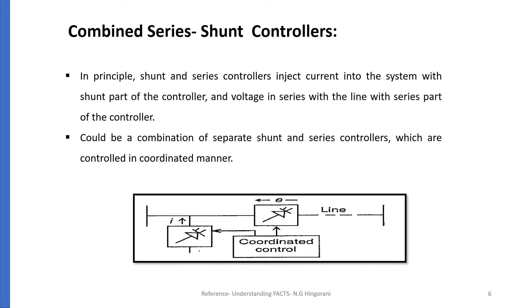Combined Series-Shunt Controllers inject current into the system with the shunt part and voltage in series with the series part. These are a combination of separate series and shunt controllers controlled in a coordinated manner, or it can be a UPFC — that is, Unified Power Flow Controller — with series and shunt elements. When shunt and series controllers are unified, there can be real power exchange between the series and shunt controllers via the power link.